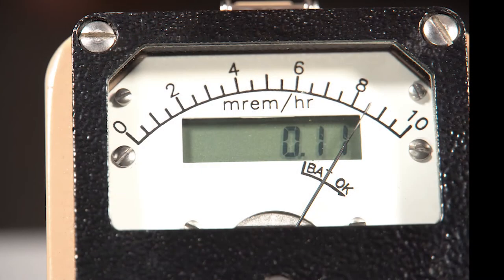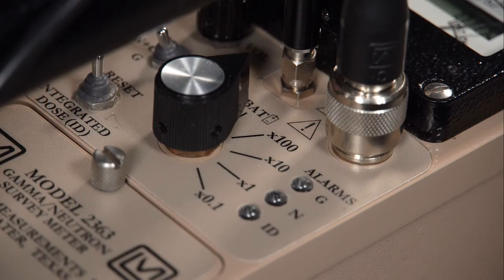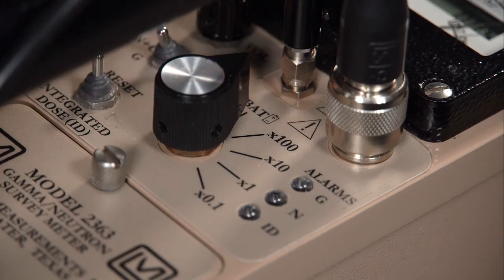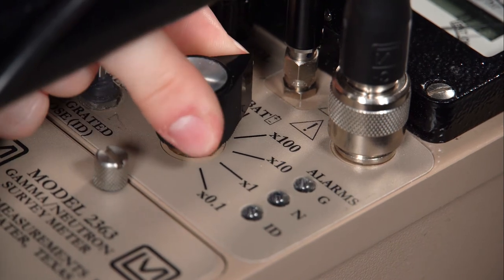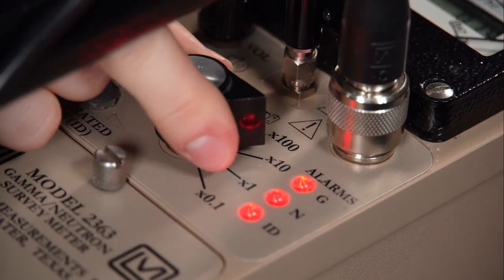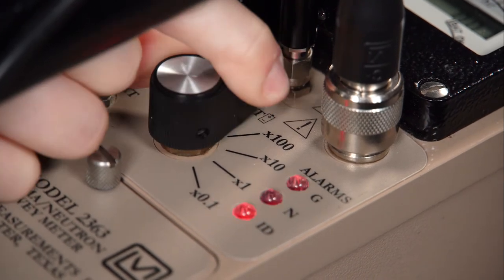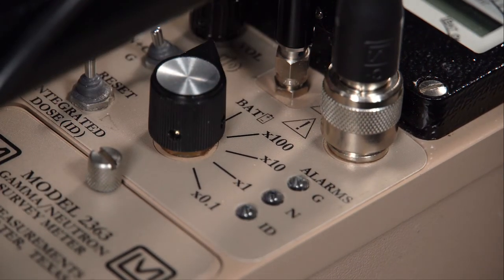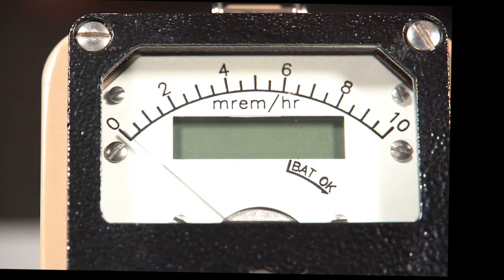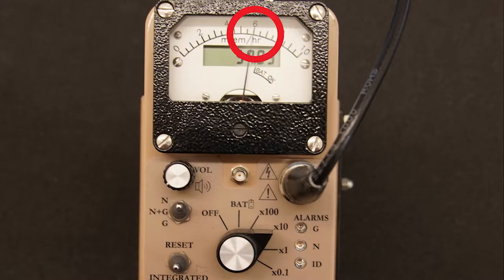Moving the range selector switch to one of the range multiplier positions—times 100, times 10, times 1, times 0.1—provides the operator with an overall measuring range of 0 to 1000 mrem per hour. Multiply the scale reading by the multiplier to determine the actual reading.